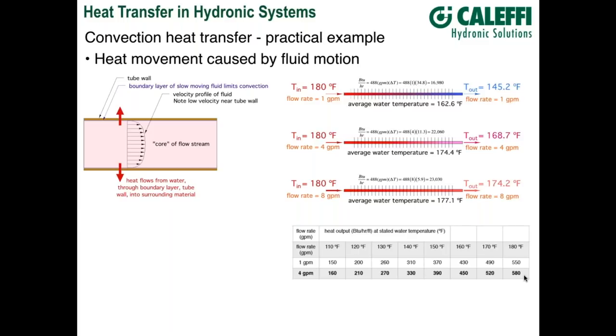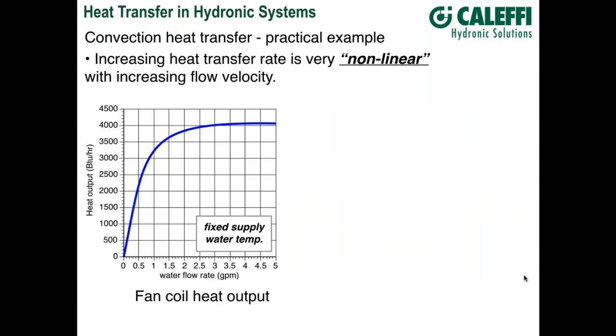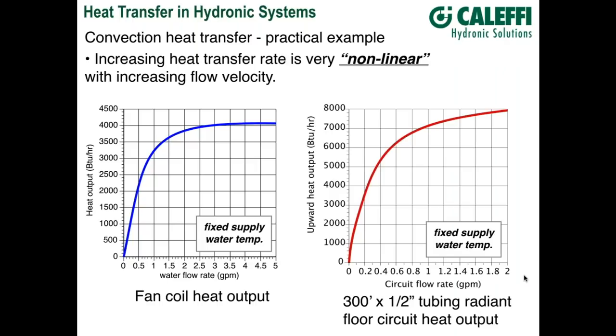Summary: heat transfer rates always increase with increasing flow velocity because of the thinning of the boundary layer and the increase in the convection coefficient. That effect is very non-linear — doubling the flow rate does not double the rate of heat transfer. Based on rating data for a small fan coil at a fixed supply water temperature, at very low flow rates you see a rapid increase in heat output, but at higher flow rates the heat output continues to go up at a diminishing rate. This is also true with other hydronic heat emitters.